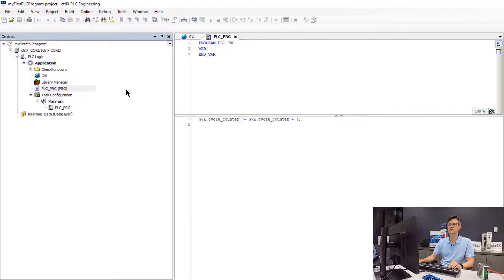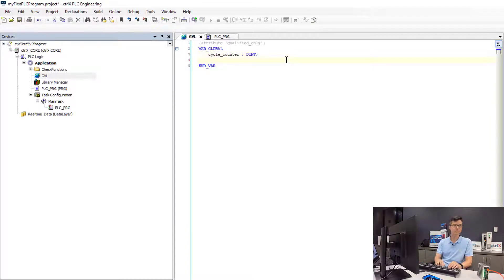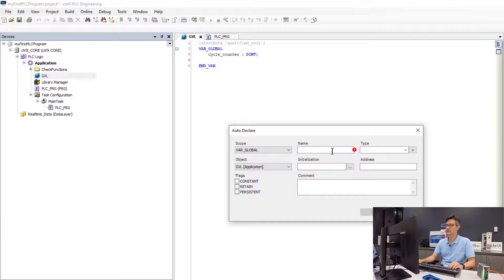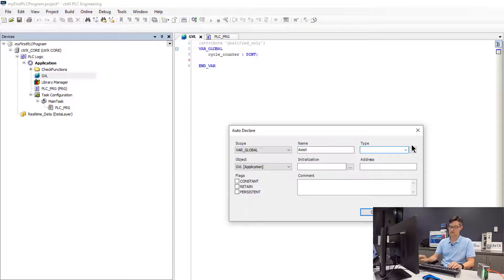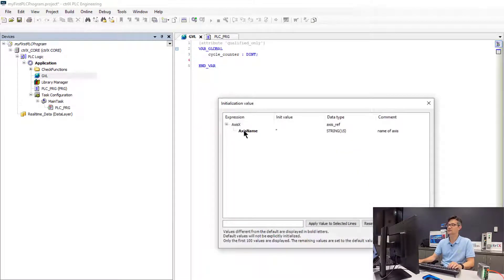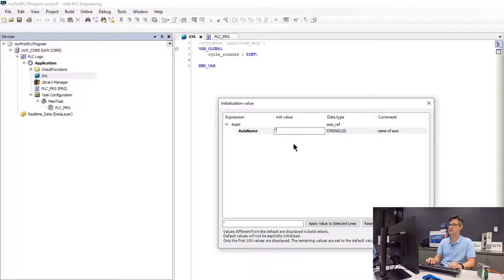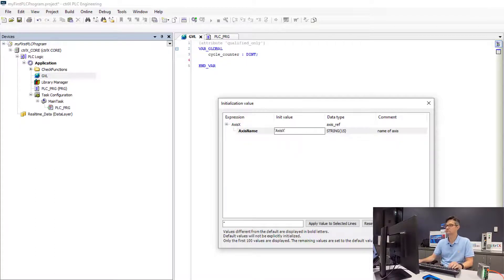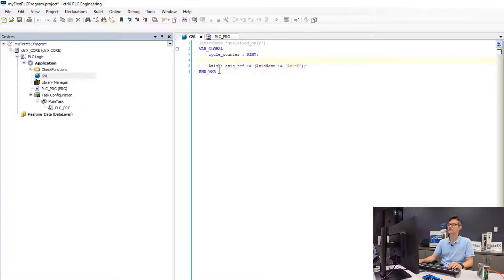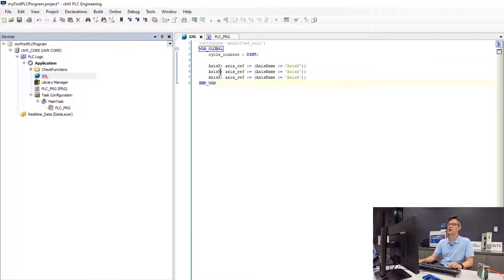So the first thing that we will do is go back into the global variable area and we will define our AxisRef variables. A simple way to declare your variables quickly is to use an auto declare with the Shift F2 key. So I will go ahead and declare my Axis names with this wizard. So Axis X of type AxisRef, we will use for the initialization. We have to initialize the name of our axes using a string with the same name that we had configured in the Motion app. So now that we have the declaration for Axis X, we will go ahead and copy and paste it. We will create our definitions for Y and Z.